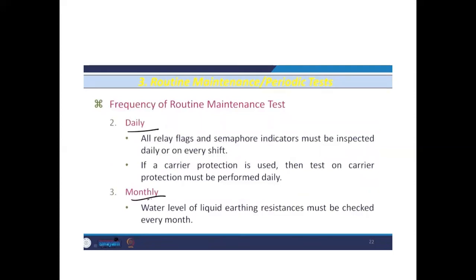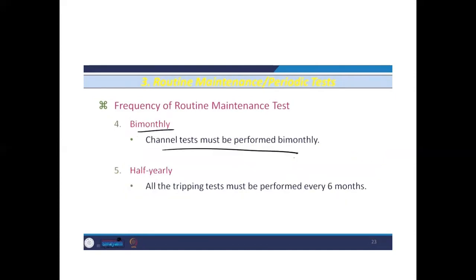All relay flags and semaphore indicators must be inspected daily. Okay, so all flags should be checked on a daily basis. If a carrier protection is used, then the test on carrier protection must be performed daily. Okay, so carrier protection should be inspected on a daily basis. Now monthly: the water level of the liquid earthing resistance must be checked every month. Okay, so the liquid of the earth resistance should be checked on a monthly basis.